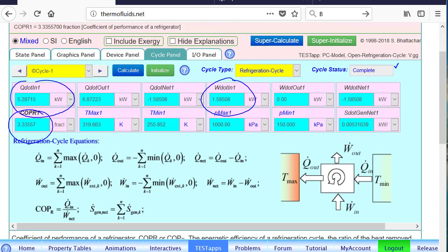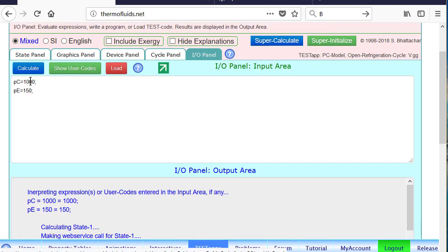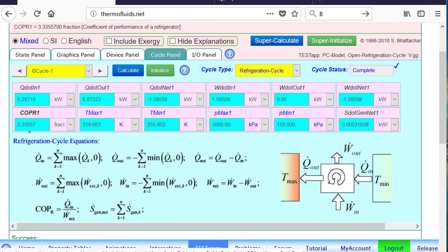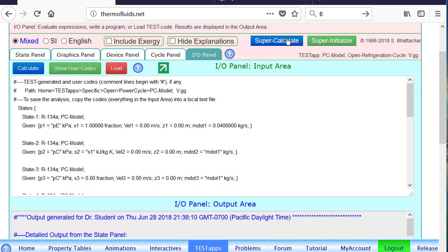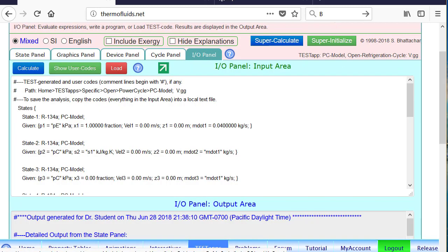Right now the COP is 3.33. Let's raise the condenser pressure — instead of 1000 kPa, we set it to 1500 kPa. Let's do a supercalculate and check. The COP goes down from 3.33 to 2.22, confirming our prediction. Likewise, you can do any number of what-if studies using this app. If you put the suitable parameters in the IO panel, you can very easily change the variable and see its effect on overall quantities.